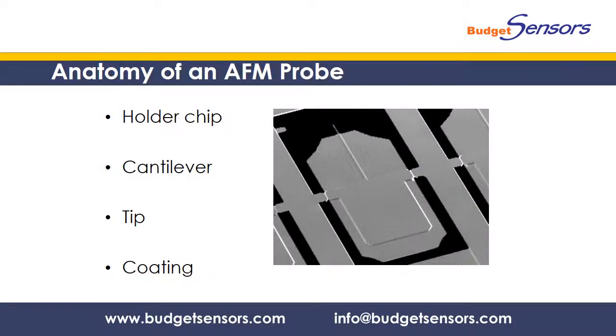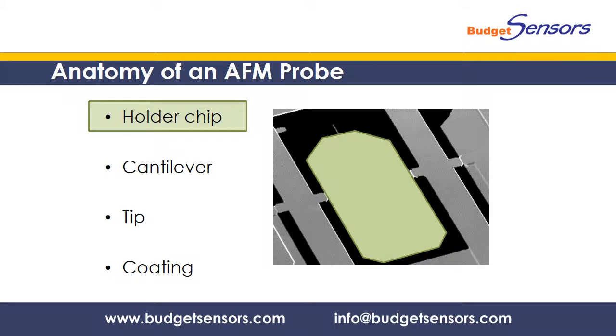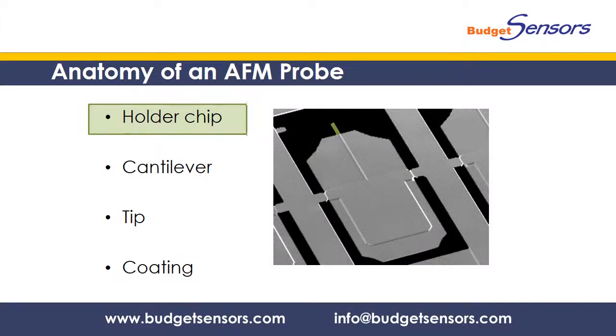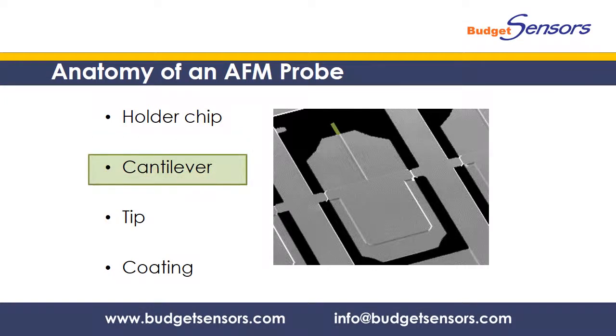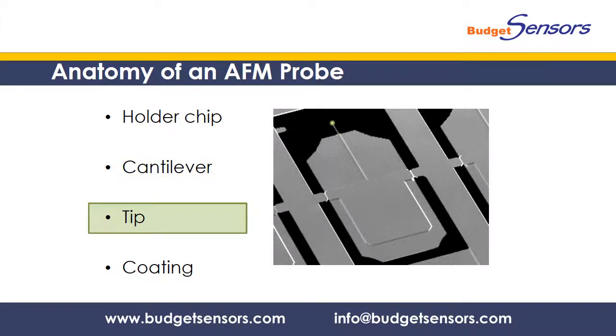Let us look closer. The AFM probe has several main components. The largest part is the holder chip. The chip is so large relative to the rest of the probe in part to allow easy handling of the probe with tweezers. At one end of the chip is the cantilever, a small flexible rectangular or triangular element that helps the AFM system track the interaction of the tip with the sample surface. Then comes the tip itself.